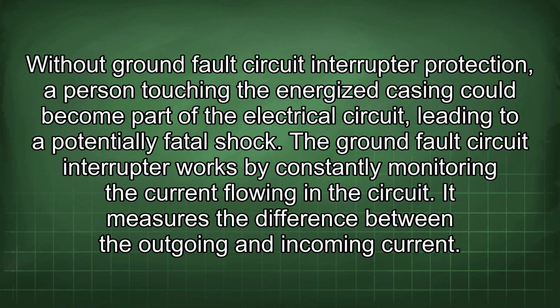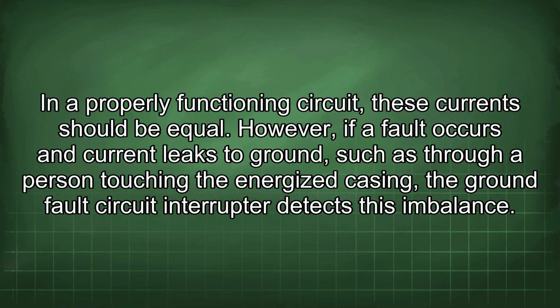The ground fault circuit interrupter works by constantly monitoring the current flowing in the circuit. It measures the difference between the outgoing and incoming current. In a properly functioning circuit, these currents should be equal. However, if a fault occurs and current leaks to ground, such as through a person touching the energized casing, the ground fault circuit interrupter detects this imbalance.